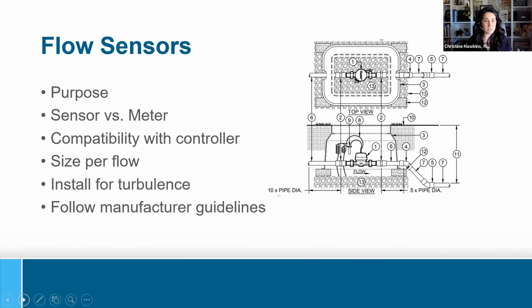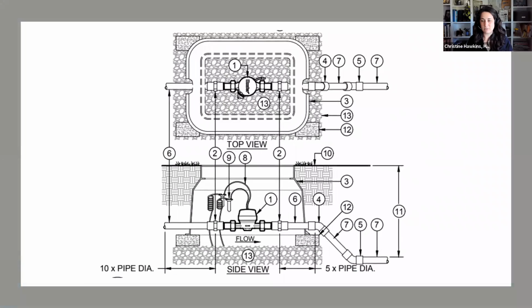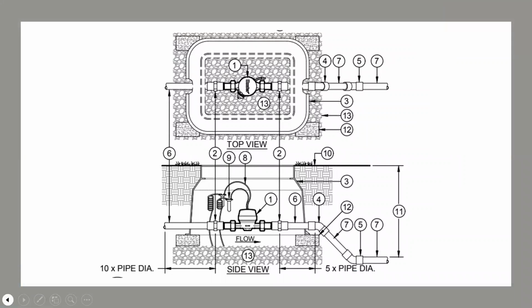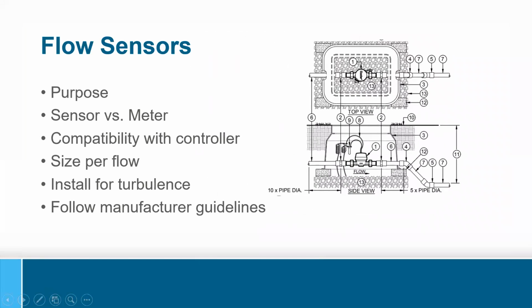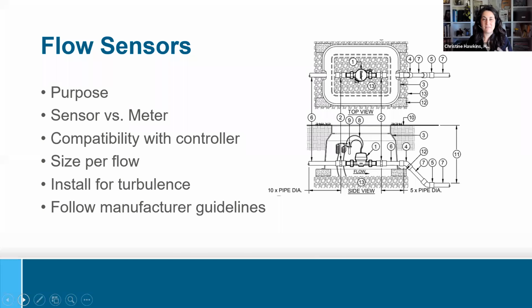The flow sensor connects to an irrigation controller. It's simple right there. Flow meters tend to... Oh, can you back that up, Kristen? You went a little quick. Thank you. Okay. Flow meters are standalone and will have a dial readout on the top for total flow, and the little leak detection spinner. If you've ever looked at one, there's a little triangle leak detection spinner there. They're usually standalone. They can be used by billing agencies, such as Luke talked about.